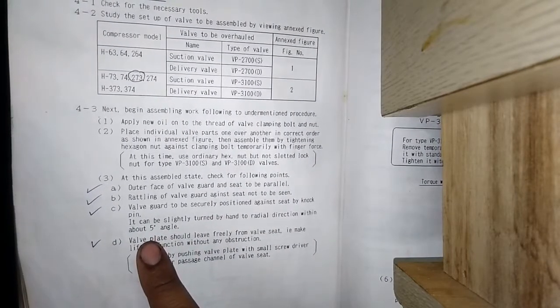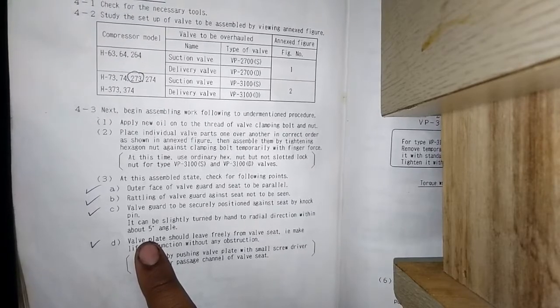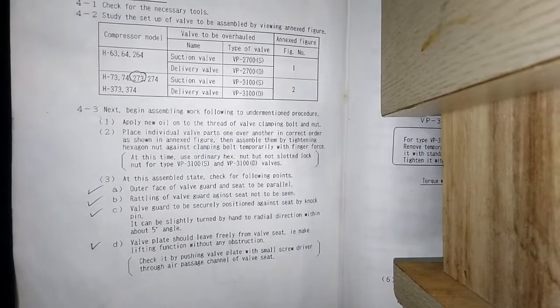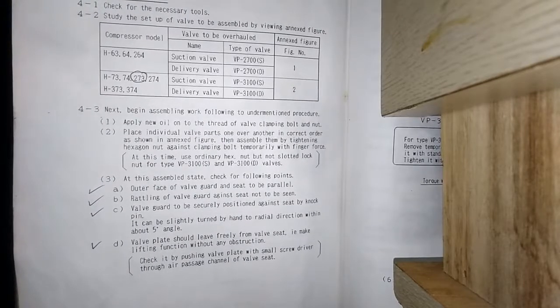I will show you how to check this. Valve guard to be secured in position by the knock pin, which fits in the hole. The valve plate should lift freely from the valve seat, making the lifting function without any obstruction. This will be checked with the help of a screwdriver.